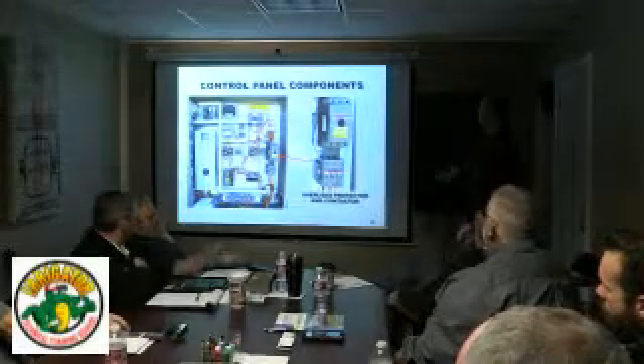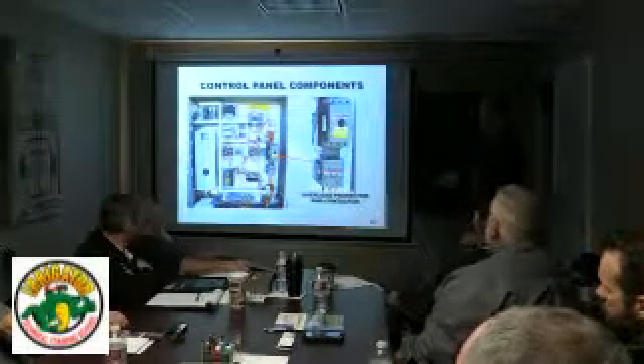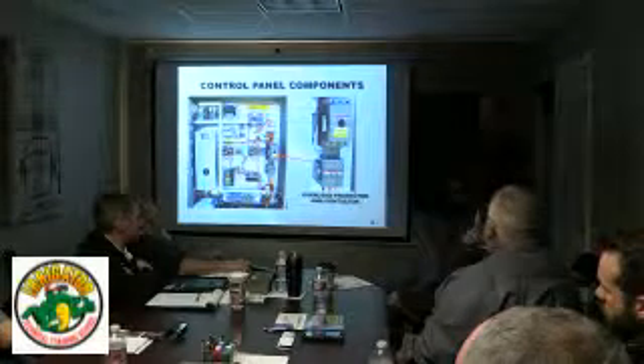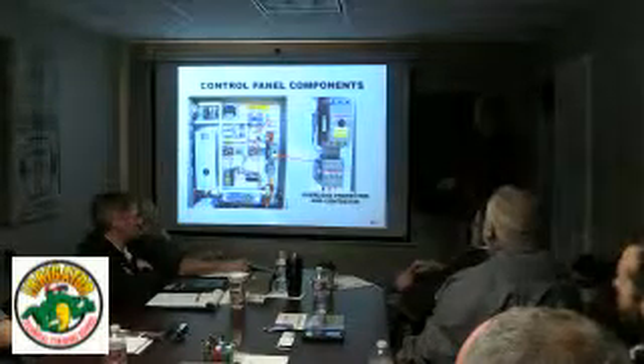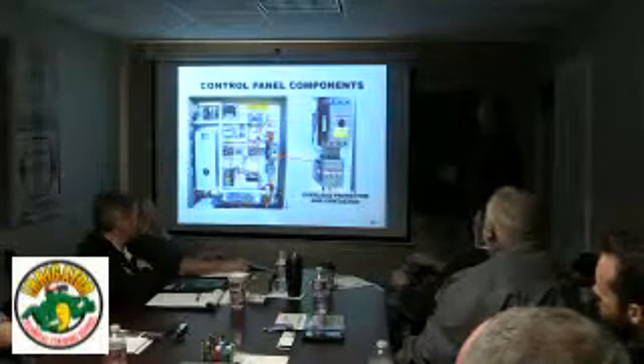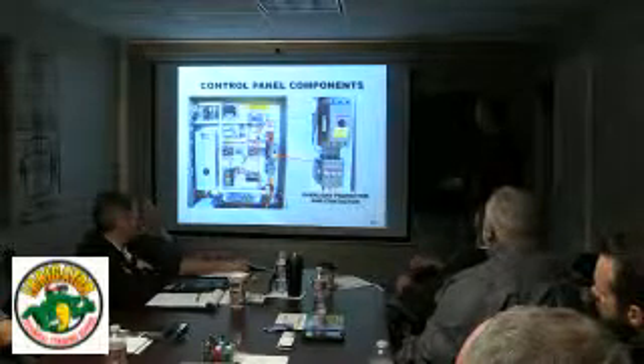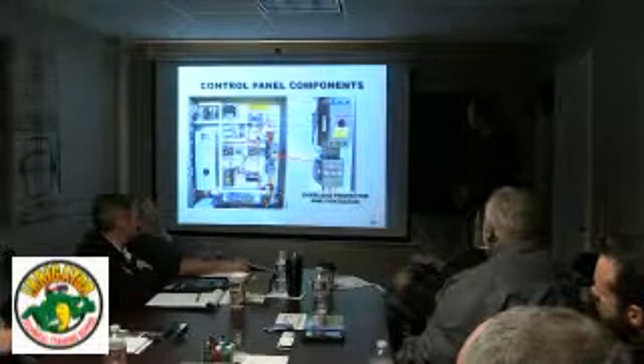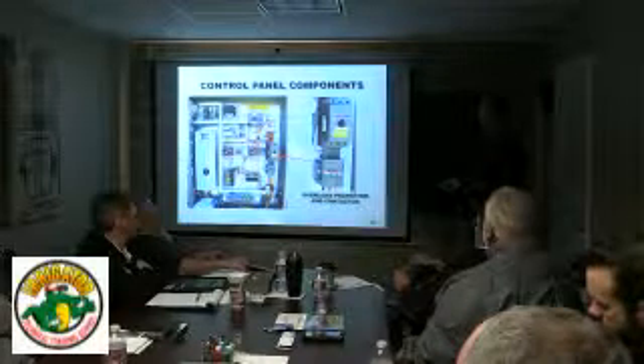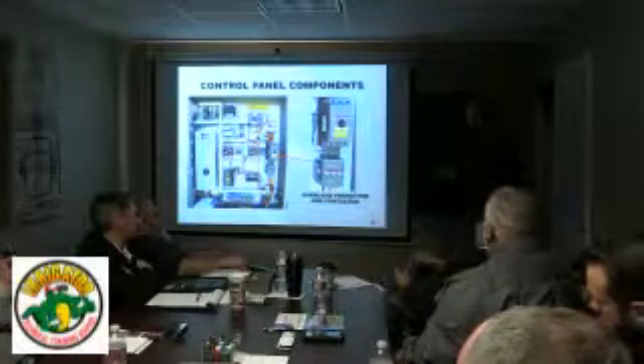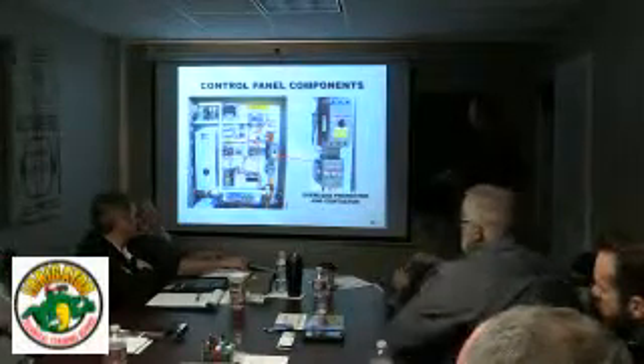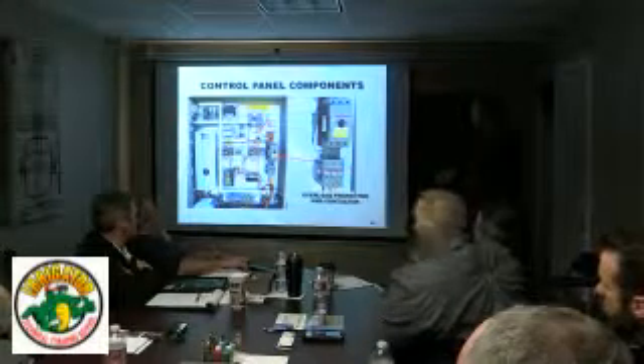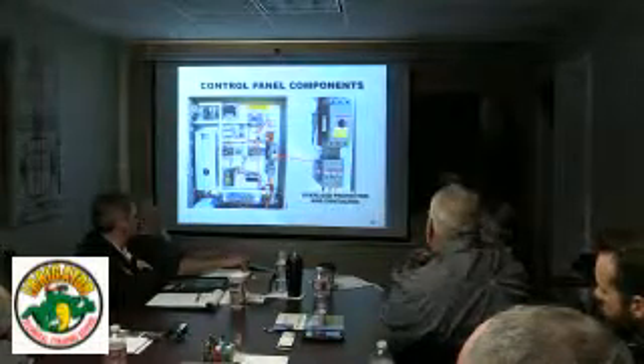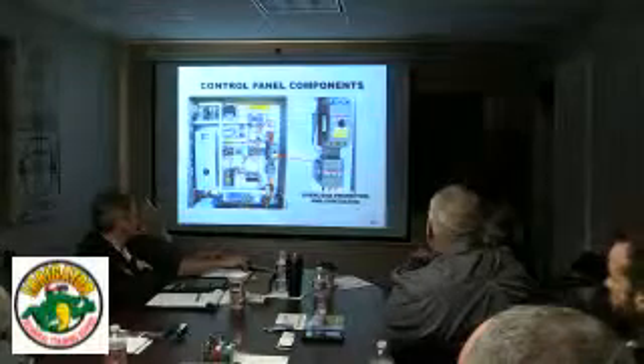Another thing that this will do is we have an auxiliary contact down here, and that's simply an input to the PLC that says this contactor is energized. So if this trips and this opens, then we know that this is faulted, that it's tripped. Actually, that's just going to signal to the PLC that this is pulled in or not.